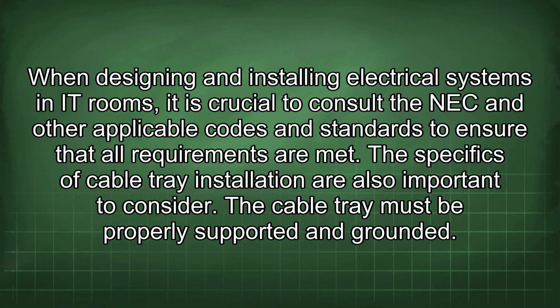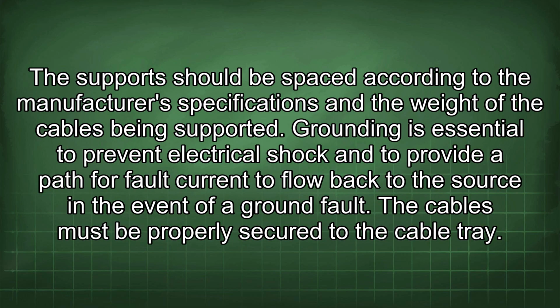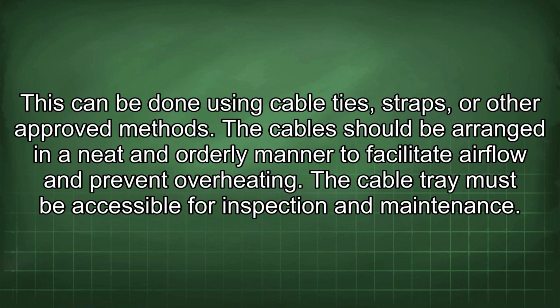The specifics of cable tray installation are also important to consider. The cable tray must be properly supported and grounded. The support should be spaced according to the manufacturer's specifications and the weight of the cables being supported. Grounding is essential to prevent electrical shock and to provide a path for fault current to flow back to the source in the event of a ground fault. The cables must be properly secured to the cable tray. This can be done using cable ties, straps, or other approved methods. The cable should be arranged in a neat and orderly manner to facilitate airflow and prevent overheating.